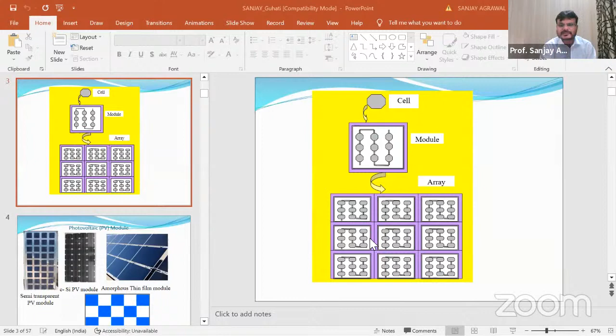Now you need 8.8 ampere current. That means a string of 18 PV modules connected in series, and a similar string, with both strings connected in parallel. This is how you can find out how many PV modules are required and how you will connect them in series or parallel.